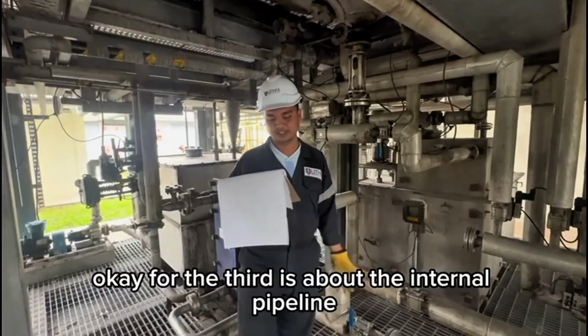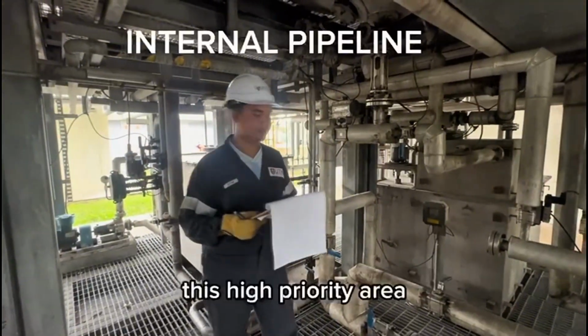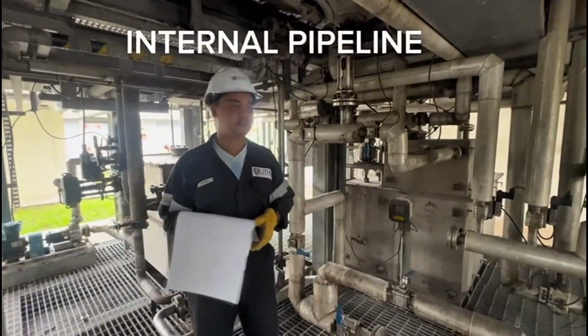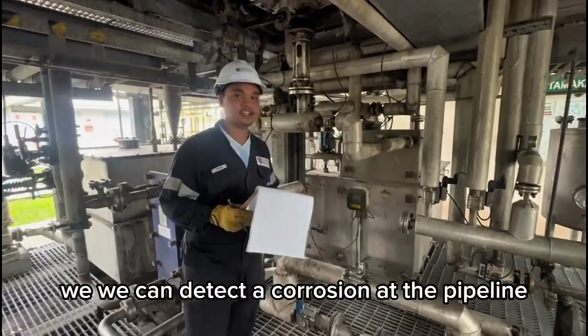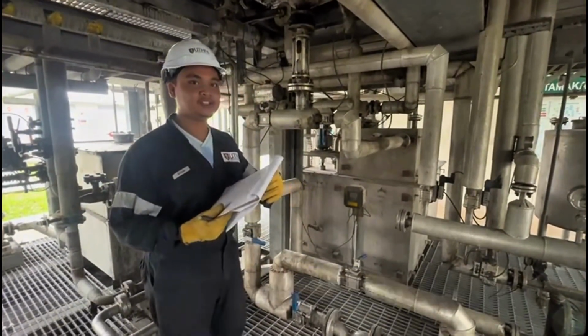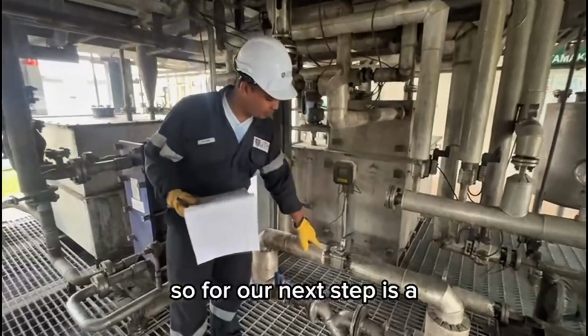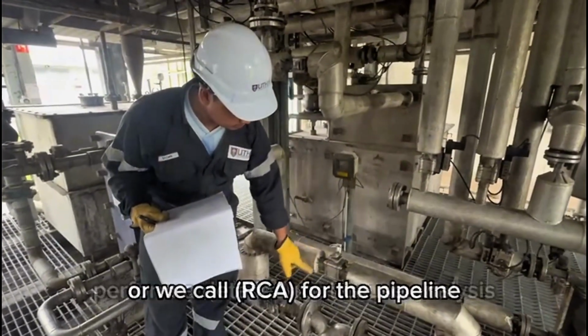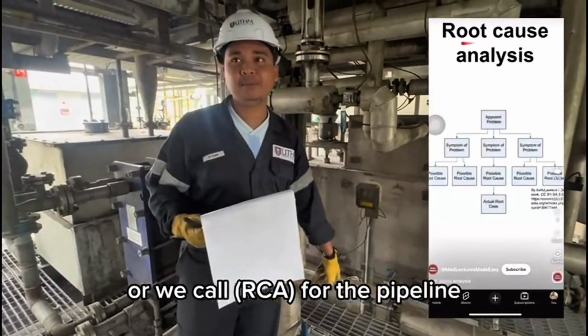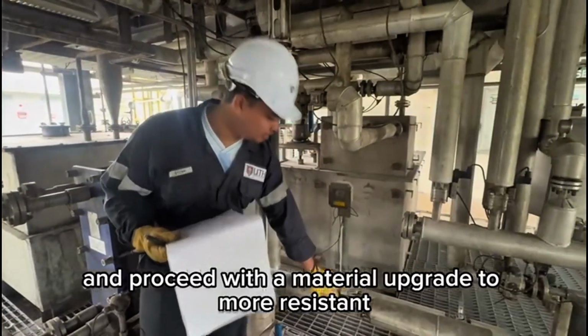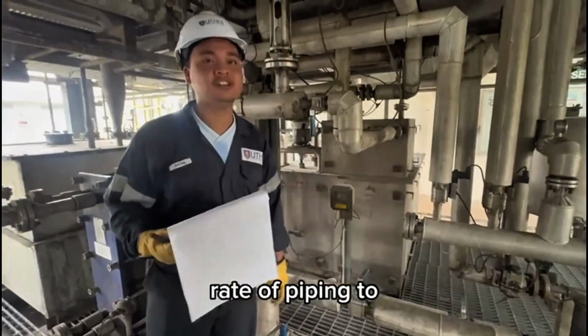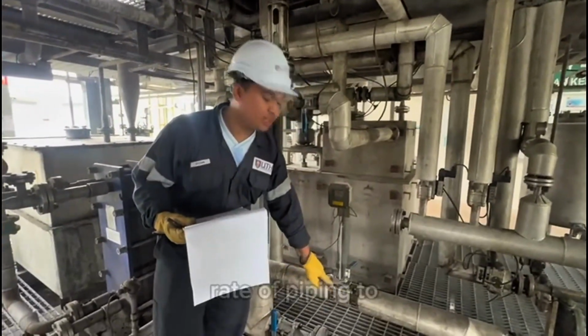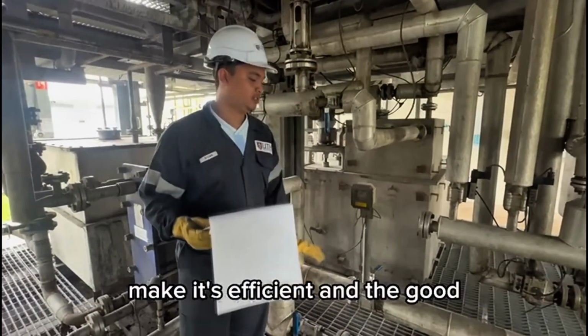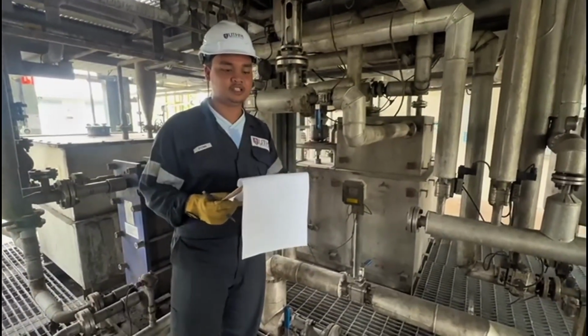Okay, the third is about the internal pipeline. This is a high priority area. We can detect corrosion at the pipeline. So, our next step is to perform a detailed root cause analysis, or RCA, for the pipeline, and proceed with a material upgrade to a more resistant grade of piping to make it efficient and good quality.